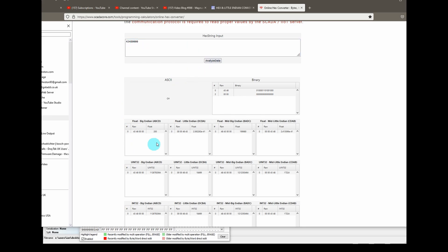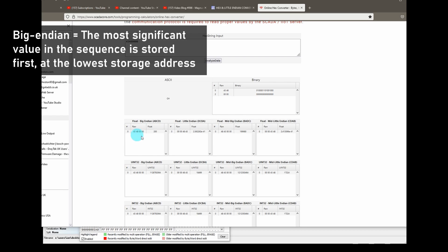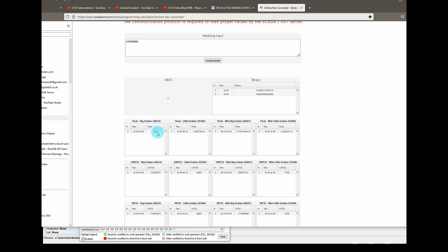They're suggesting I change C8 to 4396. Let's have a look and see what location C8 holds for me. C8 is 4348. What do those numbers mean? Here's an online calculator where you input the hex string. 4348, analyze the data. The float value in big endian is 200. If I change it to 4396, it changes to 300.